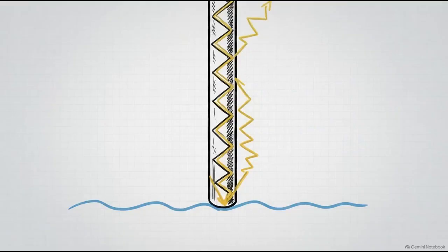But what if your liquid is highly viscous, really corrosive, or just churning with heavy foam and vapors? A standard radar signal bouncing through the air might just get scattered. That's when you bring in a guided wave radar, or GWR. Instead of shooting microwaves through the open air, the radar pulse travels directly down a physical probe, like a metal rod or a flexible cable, cutting straight through the turbulence. When that pulse hits the material surface, the energy reflects back perfectly. It really is the best of both worlds.